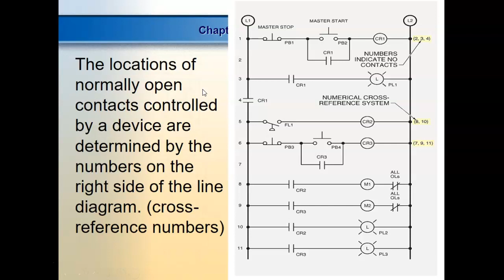Does that make sense? They're just reference numbers to tell you, hey, this is also here and here. So you can look at it and go, oh, if I energize this, I might need to make sure that these two circuits are clear from whoever's messing with them. Because are all these circuits going to be right next to each other? No, not always. You could end up with one circuit that's on the other side of the plant, right? So you really want to be careful when you're starting stuff up. Otherwise, you could shock somebody. I find that most people tend to not like getting shocked for some weird reason.